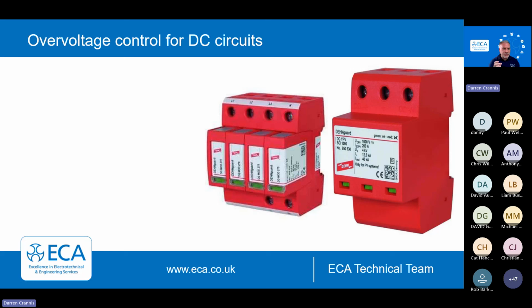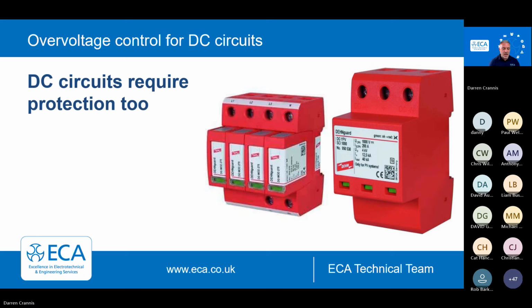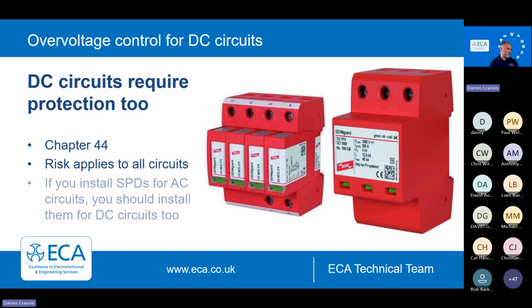And we've all been told about DC isolators, how they need to have a big clearance distance, and they have to open up rapidly to extinguish that arc. It's the same for SPDs. If you fit an AC SPD in a DC circuit, you'll find if it does operate, it will often go on fire because it's that huge sustained arc. So risk does occur. If it does, we need to apply it to our AC circuits and our DC circuits too. In terms of things like solar PV and other equipment, it may have it built in. So some inverters, for example, do have the equivalent built in. It's a conversation for you to have with the manufacturer.